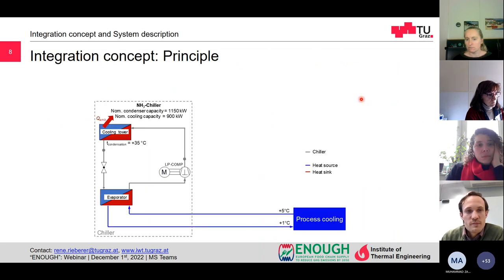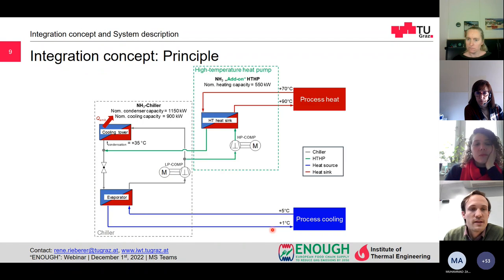Coming over to our system and the concept, we see here our chiller with the compressor and the cooling tower and the evaporator, which supplies the cold water for the process at around 1 degree Celsius. This was the demonstrator, or the system, which was already running. And the high temperature heat pump has been directly integrated into this chiller after the low pressure compressor. The refrigerant is taken here to the high pressure compressor, lifted up to a pressure and temperature level suitable for process heat supply, so here for the heat sink of up to 90 degrees Celsius. And afterwards, the refrigerant flows back here to the chiller.